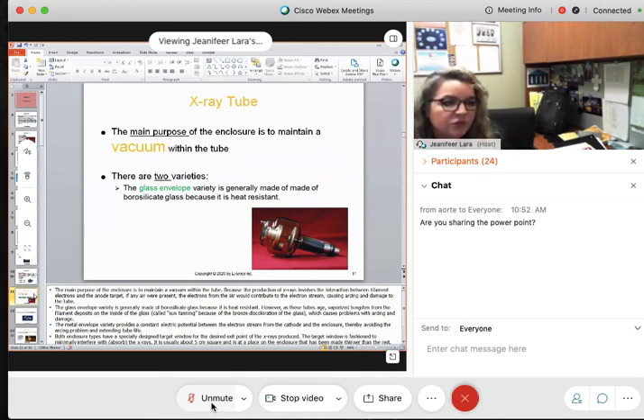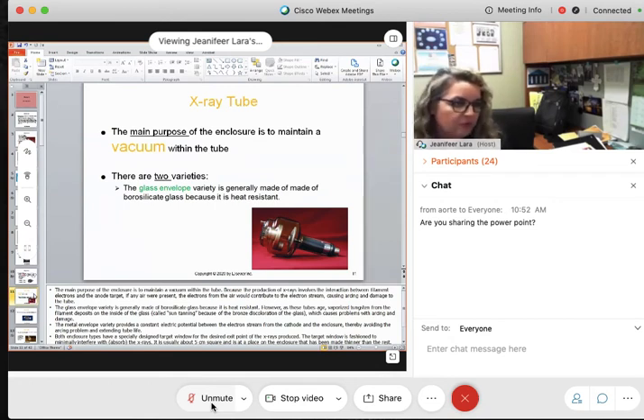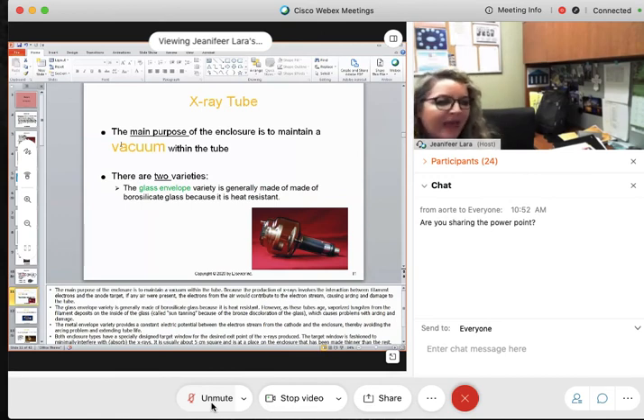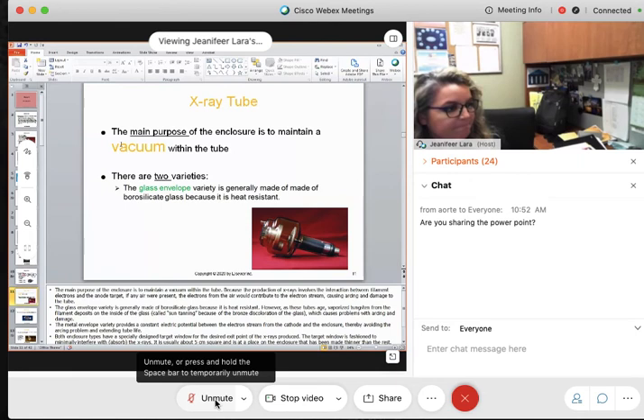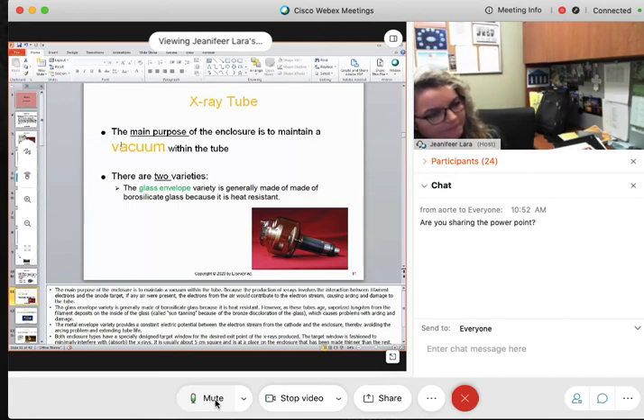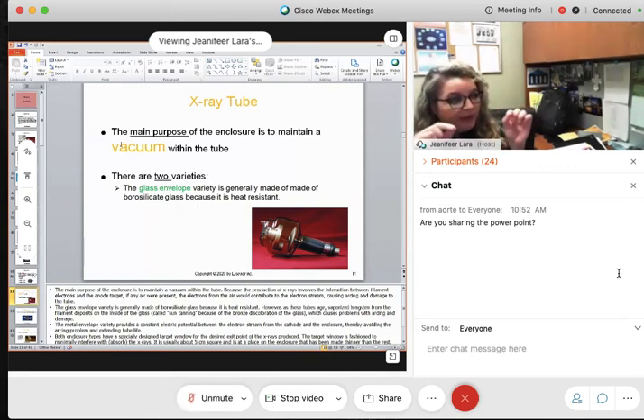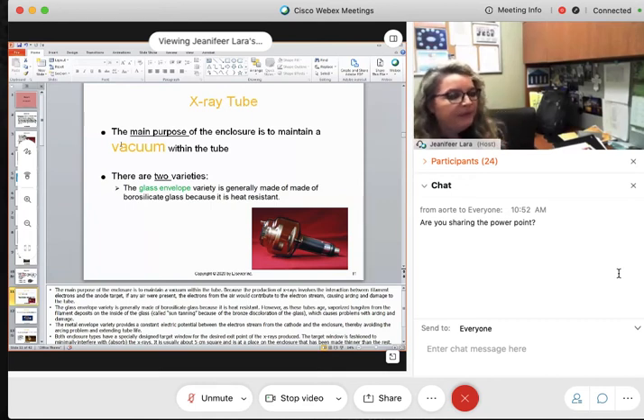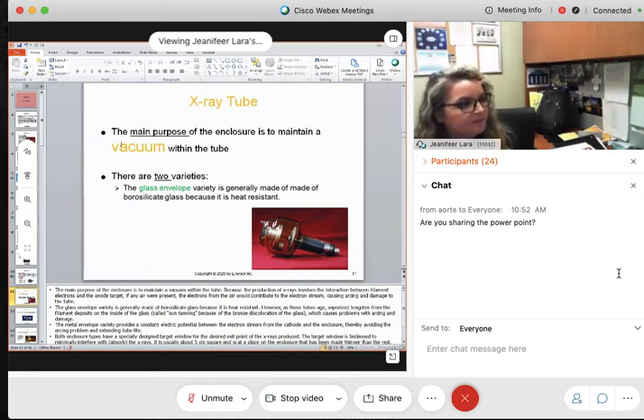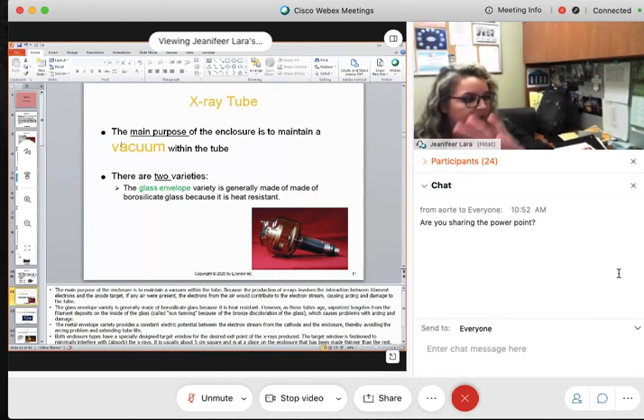The main purpose of an x-ray tube — once you crack it, it's no good. If you break it, no good. It has to have a vacuum. Why would there need to be a vacuum setting in order to create x-rays? The vacuum is to prevent any air from bumping into our electrons. We are going to have a stream of electrons and we don't want any air molecules to interfere.